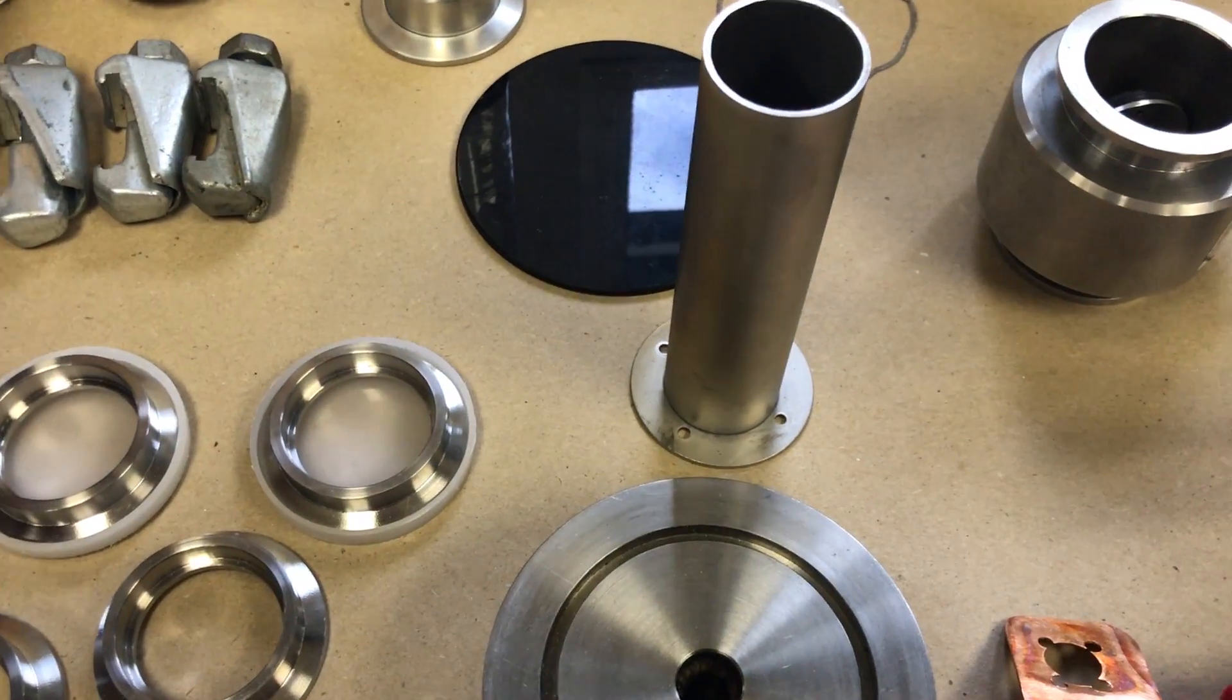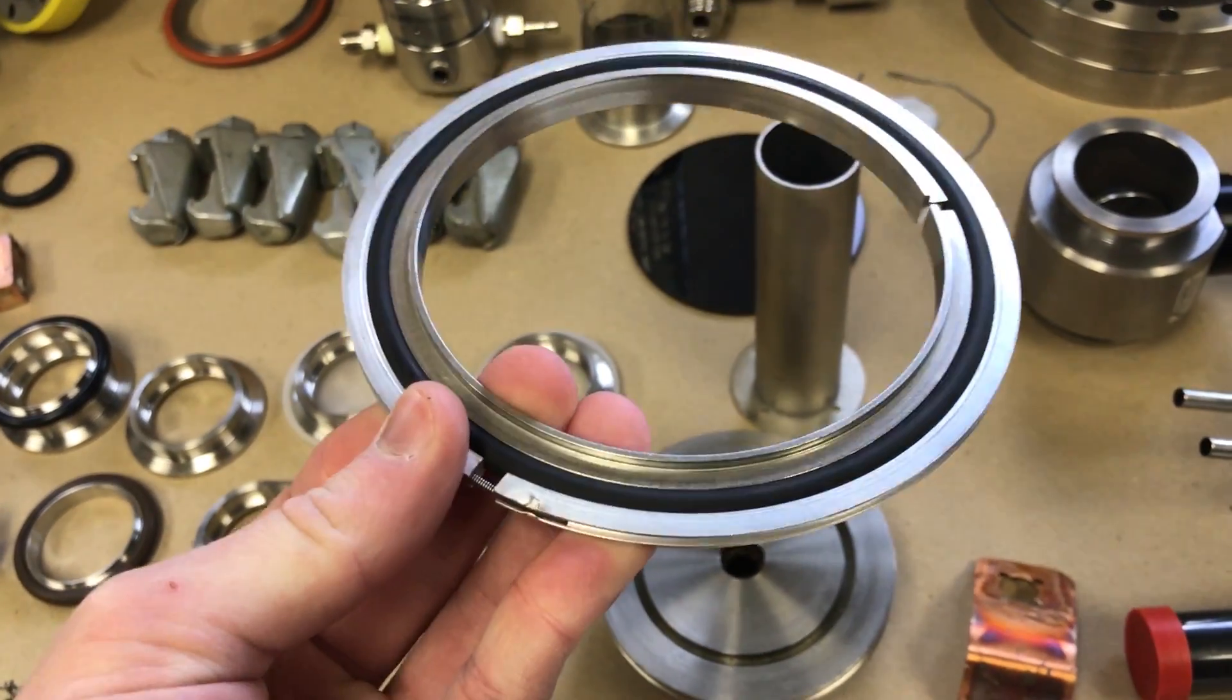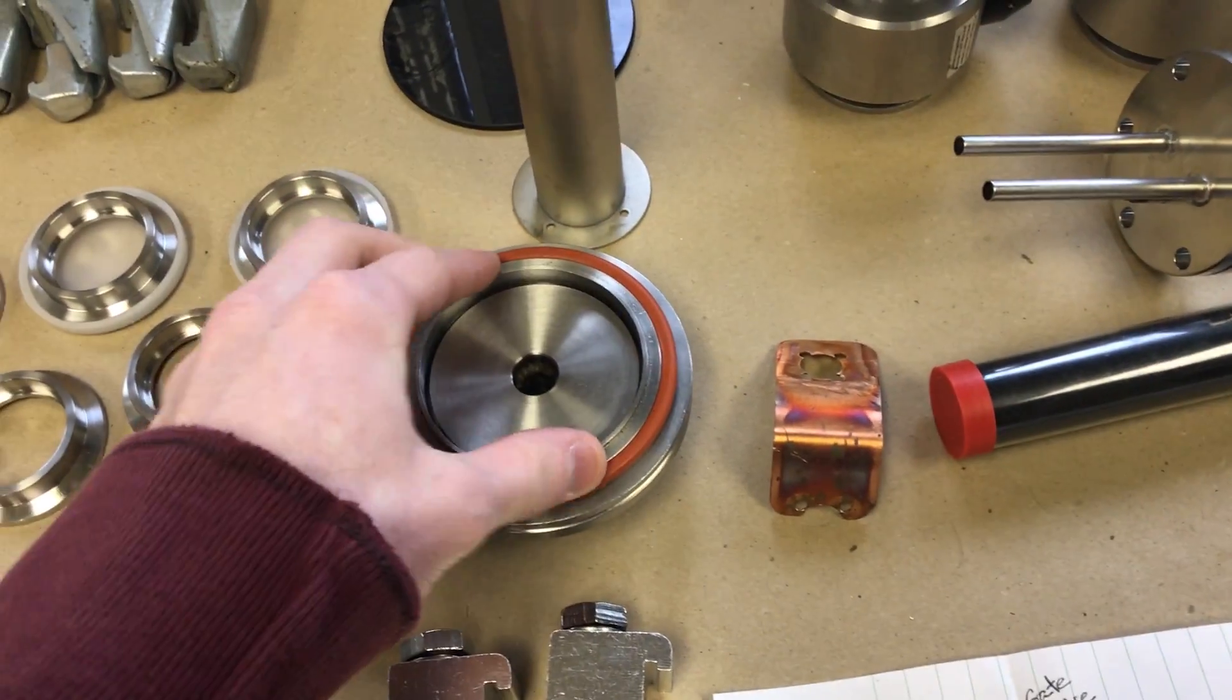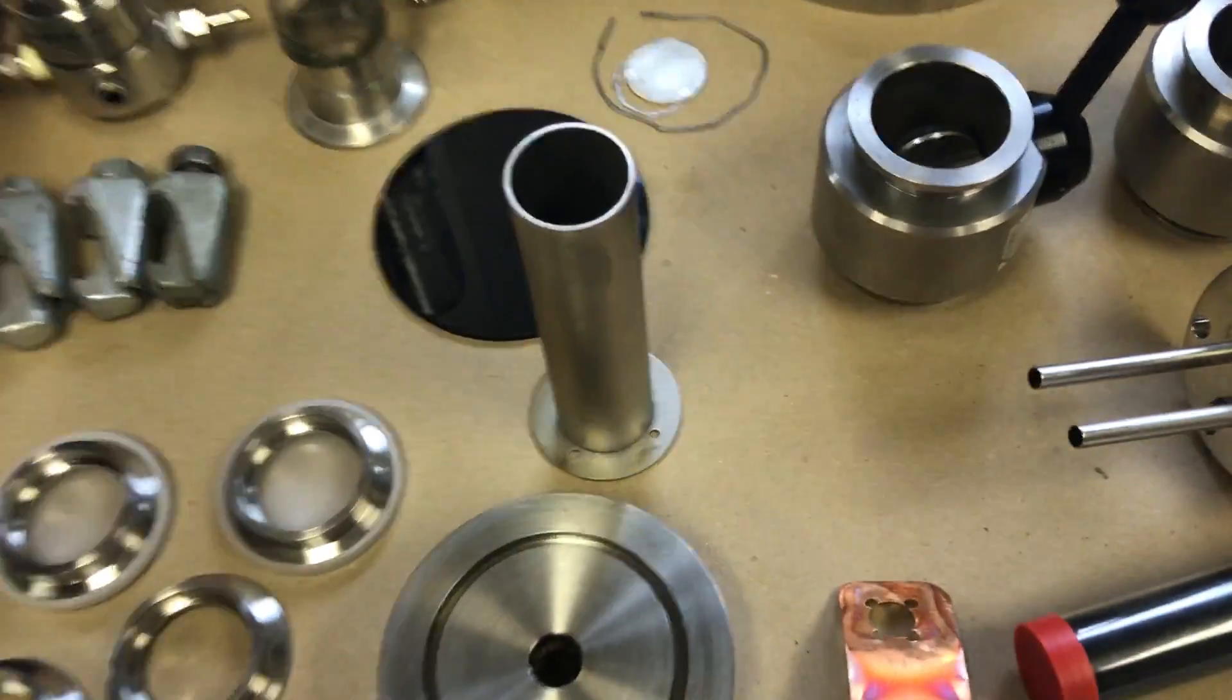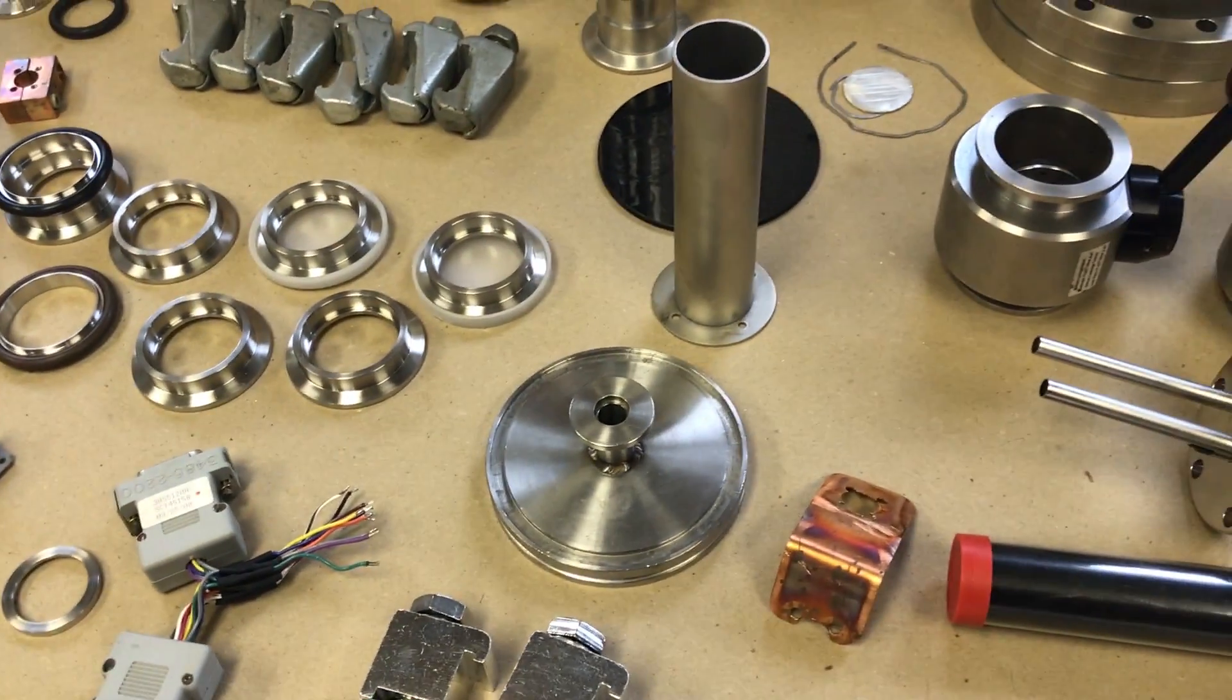It'll normally look like this, where you have an o-ring, and then you have an inner and an outer. Sometimes the inner is stainless, and the outer is an aluminum band. And this is called the centering ring assembly. And that centering ring will just fit into that groove, and it's clamped on. So that's not quite a good seal as the conflat that we just talked about.